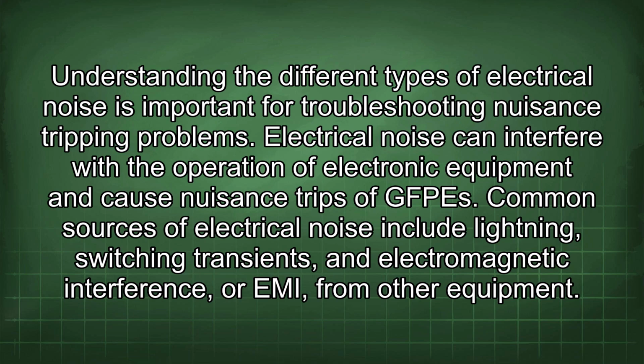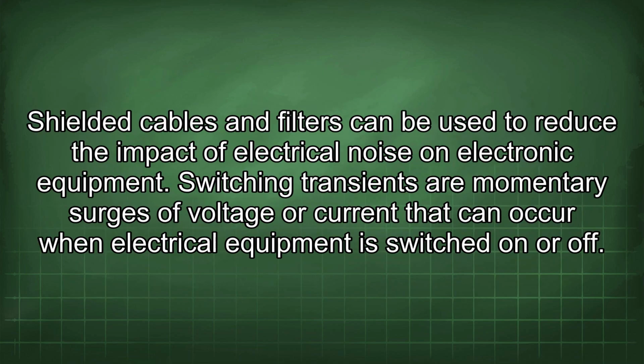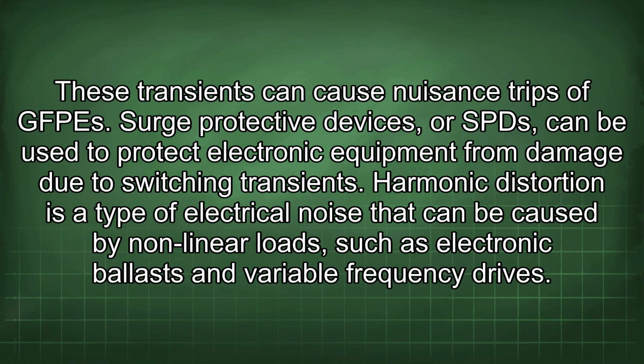Electrical noise can interfere with the operation of electronic equipment and cause nuisance trips of GFPEs. Common sources of electrical noise include lightning, switching transients, and electromagnetic interference, or EMI, from other equipment. Shielded cables and filters can be used to reduce the impact of electrical noise on electronic equipment. Switching transients are momentary surges of voltage or current that can occur when electrical equipment is switched on or off. These transients can cause nuisance trips of GFPEs. Surge protective devices, or SPDs, can be used to protect electronic equipment from damage due to switching transients.